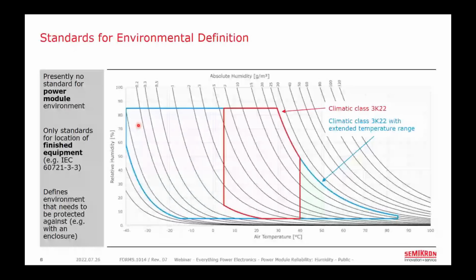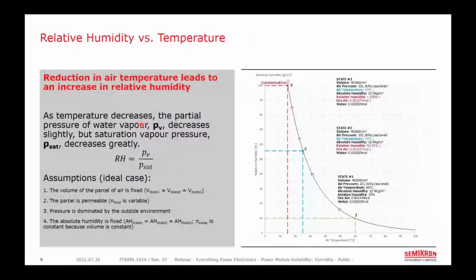Now, this IEC climatogram can also be used to illustrate how relative humidity changes with temperature. And we'll look at the transition between three states in a hypothetical environment. And to simplify this example, I'm going to have to make some assumptions here, namely that we have a permeable parcel of air with a fixed absolute humidity. So we have a fixed amount of water molecules and a fixed volume. We've arbitrarily chosen 13 grams per cubic meter of absolute humidity in a 40,000 cubic meter parcel of air.